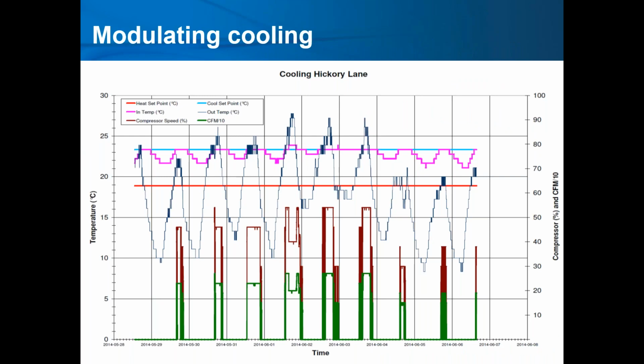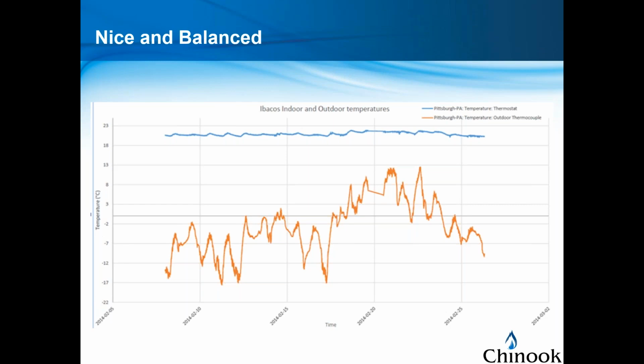This is typical of what we would see no matter what mode. This just happens to be cooling. Typically what we'll see is the CFM, the green line at the bottom, and this is over 12 days. We'll typically see the systems not running over 300 CFM in heating and 350 CFM in cooling. As long as that system's right-sized, it will run between 40 and 60% of its capacity. The pink line at the top is what we really like to see, a nice, consistent indoor temperature, while the dark blue line, the outdoor temperature, ranges from 8 degrees all the way up to 28 degrees within that period of time. We want to see a nice balanced indoor temperature over that span of time.